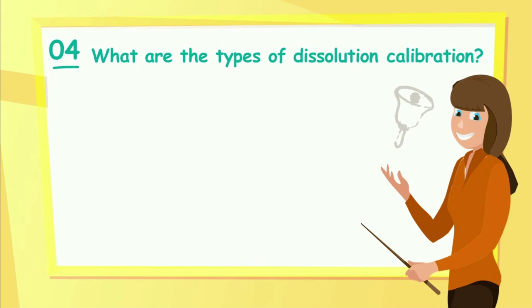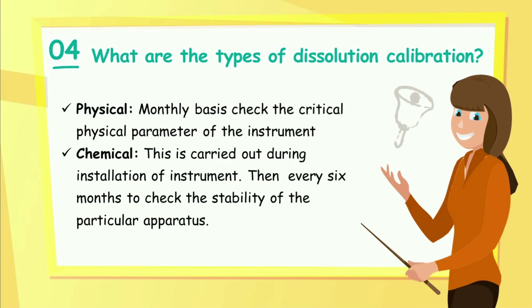There are two dissolution calibration processes, one is physical and one is chemical. Physical calibration is done on a monthly basis, checking the critical physical parameters of the instrument, like whether the thermostat is working properly, or whether the meter showing the RPM, rotation per minute, shows proper rotation per minute or less or high. These physical parameters are checked monthly on the dissolution apparatus. And the chemical calibration is carried out during the installation of the instrument, and then every 6 months to check the stability of the apparatus.